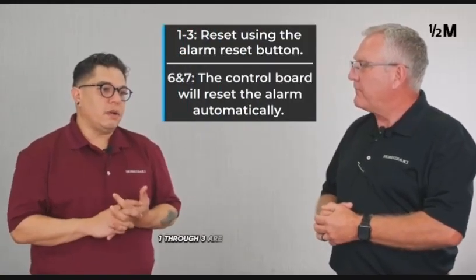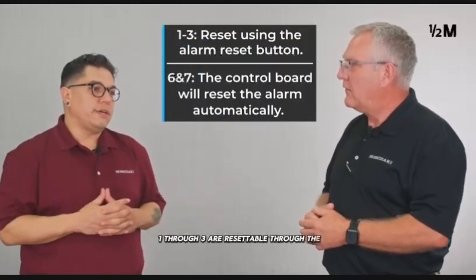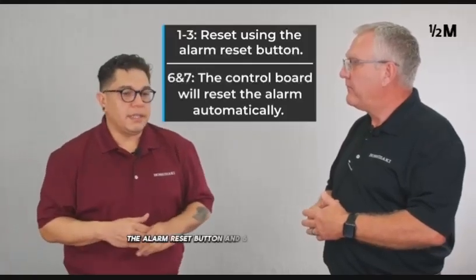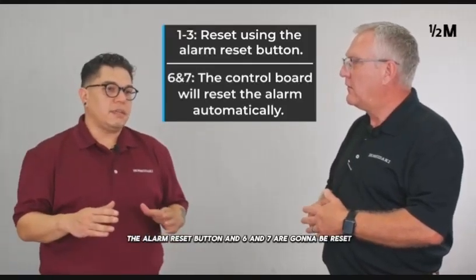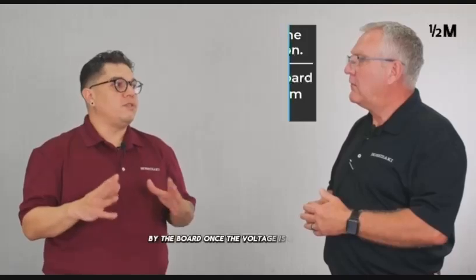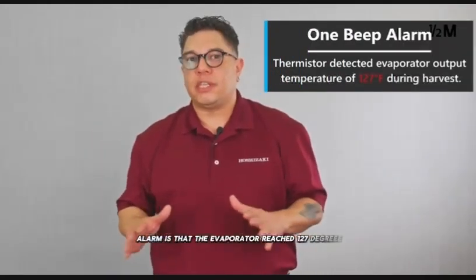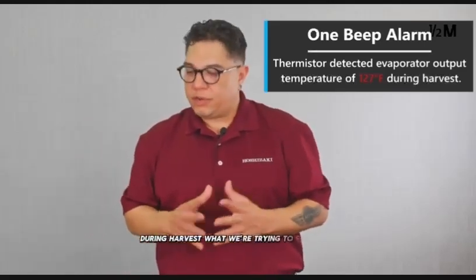1 through 3 are resettable through the alarm reset button, and 6 and 7 are going to be reset by the board once the voltage is corrected. So the 1 beep alarm is that the evaporator reached 127 degrees during harvest. What we're trying to find out is why the evaporator got so hot.